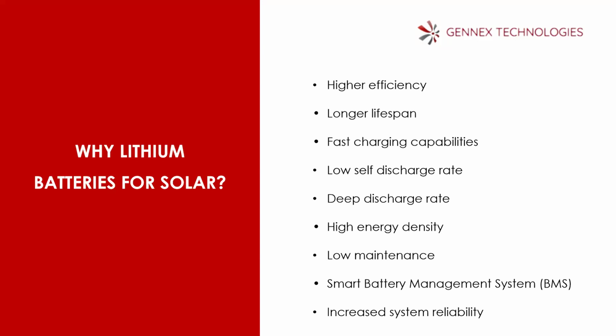For instance, if it's a 200 amp hour battery at 48 volts, that's about 10 kilowatt hours. Under normal conditions, you're supposed to charge it with maybe 20 amps or 10 amps, depending on the manufacturer's specification. But for a lithium ion battery, you can take 80 amps from it, or give it 80 amps to charge. That tells you it will charge very fast.